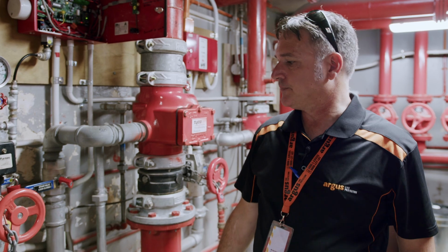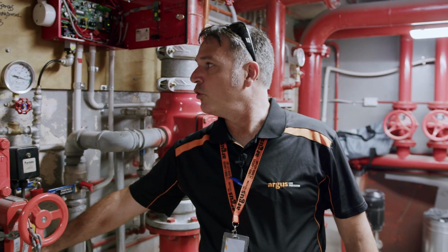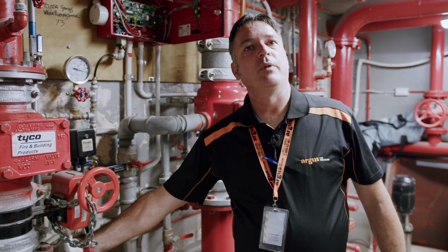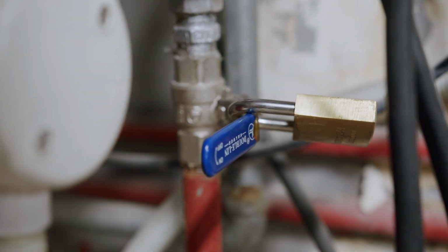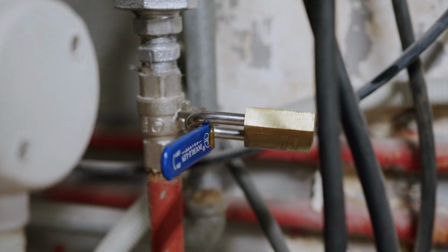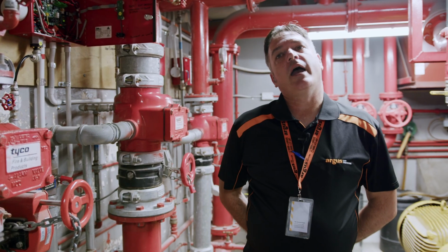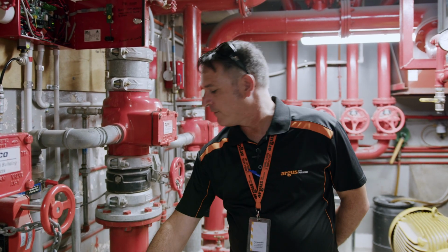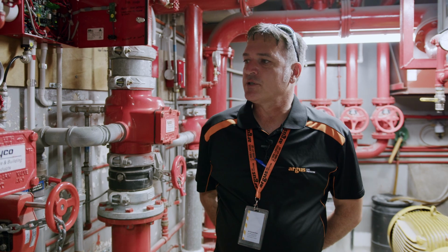The gong is located normally just here, and it is as simple as turning and opening it. They make a sound out on the road and they are useful for the fire service. Using the gong at the end of a test is important, as it also can help relieve any combined mains pressure built up in the manifold, and stop an alarm valve possibly leaking after the test.